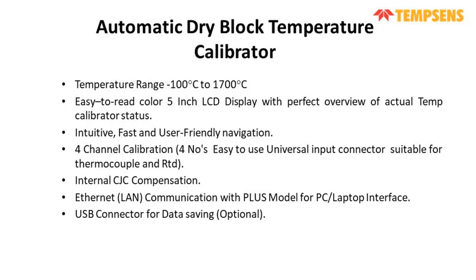Automatic dry block temperature calibrators. These calibrators come with a 5-inch LCD screen, which has two modes: a manual mode and an automatic calibration mode. In the manual mode, we can set one temperature at a time, and in the automatic calibration mode, we can set 5 temperatures at a time, with no need to check them again and again. It will complete the process, and the file will be saved. It is a very fast and user friendly navigation, with 4 channels, one master and 3 test. Then we have internal CJC compensation, Ethernet communication, and a USB connector so that you can take the data from the furnace.